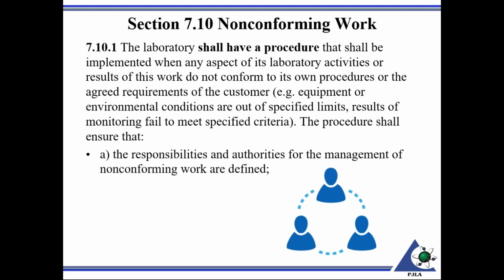So again, 7.10.1: the laboratory shall have a procedure that shall be implemented when any aspect of its laboratory activities or results of this work do not conform with its own procedures or the agreed requirements of the customers. Such as environmental conditions are out of specified limits, or results of monitoring fail to meet specific criteria. The procedure shall ensure that, so we're going to go through the listing here, but what it's saying is equipment or environmental conditions are out of specified limits.